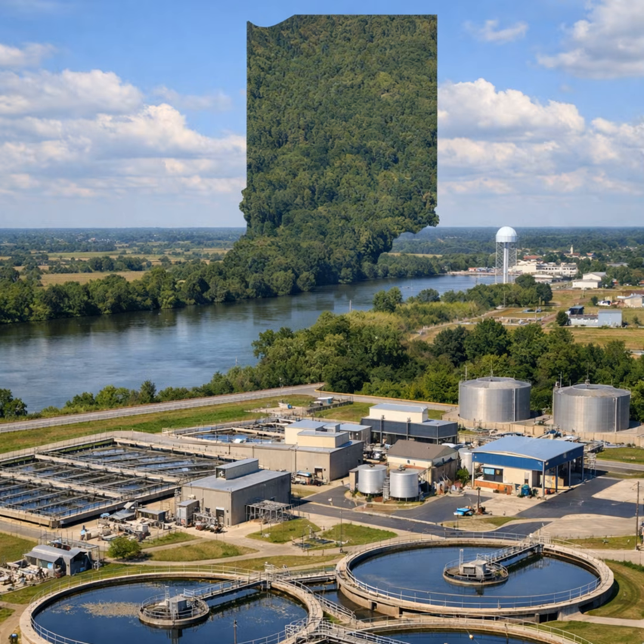Next, what is endogenous respiration? Well, in activated sludge, endogenous respiration is a situation in which living organisms oxidize some of their own cellular mass instead of new organic matter they adsorb or absorb from their environment. So it seems like they're eating their own cells, they're consuming themselves. So that's what endogenous respiration is.